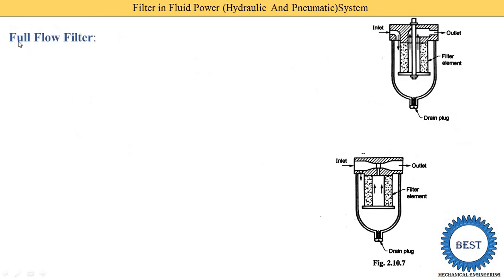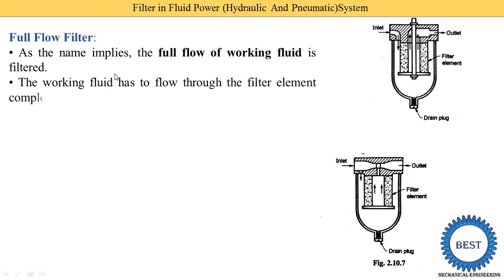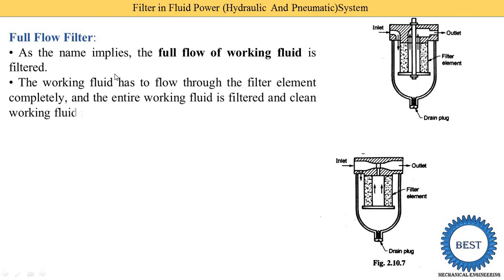The next one is the full flow filter. As the name implies, the full flow of the working fluid is filtered. The working fluid — oil in a hydraulic system, air in a pneumatic system — must flow through the filter element completely. The entire working fluid is filtered and clean working fluid comes out of the filter.